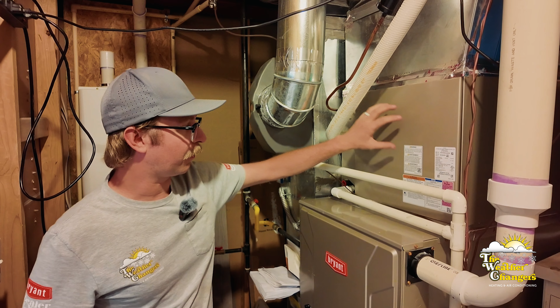Right here we got a good look at this coil, and this coil actually looks pretty great. You could see all the individual fins. So the secondary heat exchanger here is located above this blower, right about here. So what we're going to do is we're going to put our scope into the wheel of the blower, and then we're going to rotate it until the coil is visible. And this one you can see does have a little bit of stuff on it, so we're going to pull this blower out and give it a good clean.